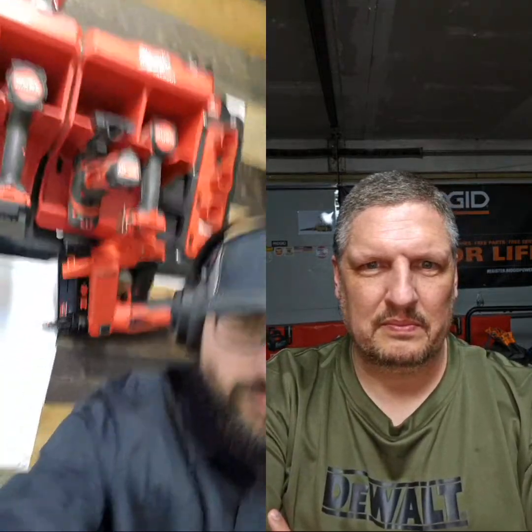So they said, can you change out this arc fault breaker? And I did my diligence, and I pulled the receptacle away from the wall. I pulled it out, and it almost fell apart in my hand, and I almost changed out that arc fault breaker to a standard breaker. So whenever I think about whether something is nuisance tripping, thankfully that story stops me from just doing what's easy. And I get my multimeter out and actually diagnose the circuit like you should.